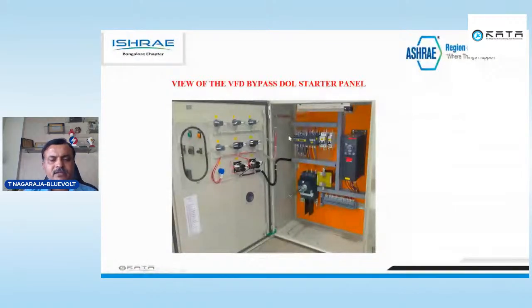See, some manufacturers give 2 contactors, some give 3 contactors. To save the VFD, they provide contactors on both input and output sides. This uses an MCCB with the VFD bypass starter. So some people use both the VFD input and output contactors to isolate it, so that whatever the number of hours your VFD is not switched on, the voltage will not go. What will happen if the voltage is continuously going 24/7, even if the motor runs 6 hours or 8 hours a day? For the balance hours also the voltage continuously goes, and your electronic components may get damaged. Due to this, it is good to isolate both sides so that the power supply also cuts off to the VFD.